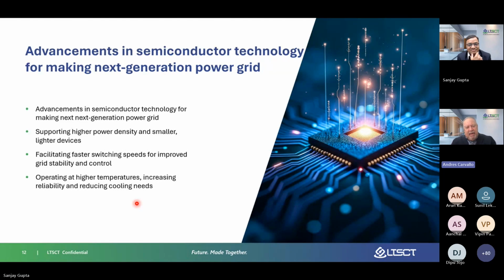But the truth is that semiconductors and solid state devices can add great value, because we're moving from a somewhat slow, traditional one-way flow grid where not much is happening, to one where now at the edge of the grid, with solar panels, Teslas, gaming stations, and all the fluctuation going on, is transforming how the grid behaves because of harmonics, modulation, and power quality. So you need new materials, you've got to go beyond silicon and take advantage of things like silicon carbide or gallium nitride or other wide band gap materials that have 10 times, 20 times better energy efficiency.